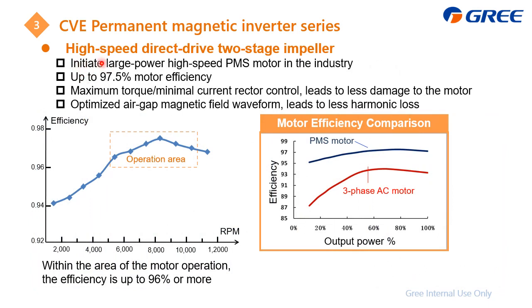First, it is the first time we apply a large power, high speed PMS motor in a centrifugal chiller. Here is the compressor RPM and here is the system operation efficiency. We always make the system operate in this area, where the efficiency is highest. Next, it has maximum torque or minimum current control, which leads to less damage to the motor. Besides, we optimize the air gap in the magnetic field, which leads to less harmonic loss. Here is the comparison between the PMS motor and the AC inverter, and you can find it is definitely higher.